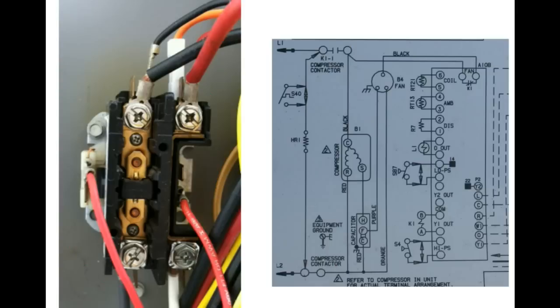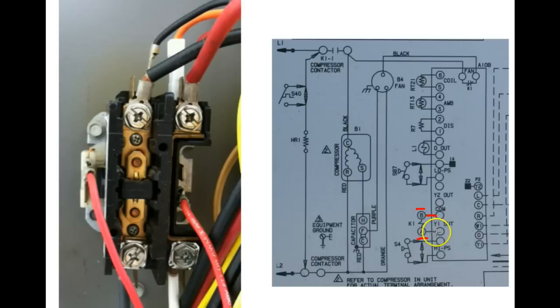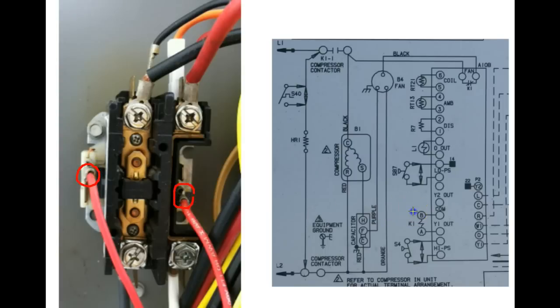The first schematic symbol we're going to look at: Lennox uses this symbol right here — this little zigzag — which represents the coil of the contactor. That is what is used to activate the contactor. We have connection A and connection B. You can see the wire colors coming out from Y1 and common aren't shown here, but with a contactor the wires that activate the coil are always on the small spade connectors on the side, especially in a residential system. That connection is represented by this zigzag schematic symbol.